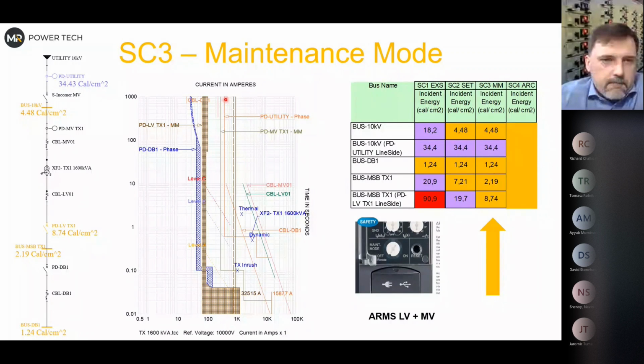I don't know if you see the difference, but I changed the settings of the medium voltage relay and you see the changed settings of the low voltage breaker. This gives us changes because the only thing that will change is the line side of the low voltage switchgear and the low voltage switchgear itself. So now you see the drop from 7 to 2 calories and from 19 to 8. That's still a significant difference, and we still utilize what we have. Maybe we have to change the trip unit here, depending on what's possible.